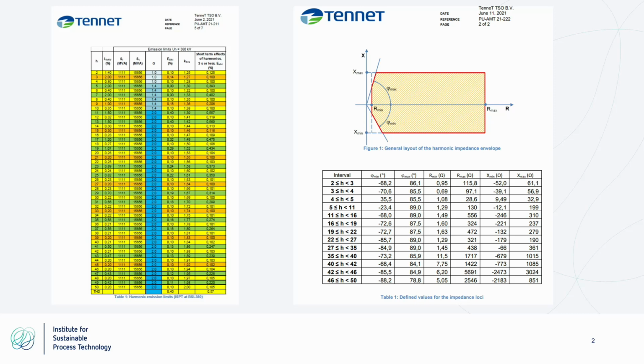Of course, they have a planning level, and due to the fact that the 1 gigawatt plant is not the complete apparent power at that substation, there is a factor, the one in blue, and that factor is applied to the planning level. That gives the total harmonic distortion you are allowed to make at that point of connection. That is the limit you have to take care of.